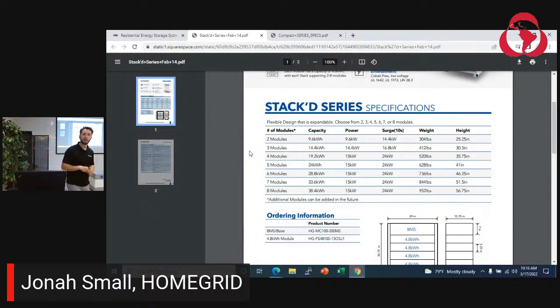Gotcha. So it's confusing the surge and the capacity. Sorry, yeah. So the surge is even higher. If you have 3 modules in a stack, the surge is 16.8. And if you go to 4 modules, that's where we have a 24 kilowatt surge. So on our 19.2 kilowatt hour battery, which is 4 of the white Legos, we can do 15 kilowatts continuous and a 24 kilowatt surge, which is fantastic performance.